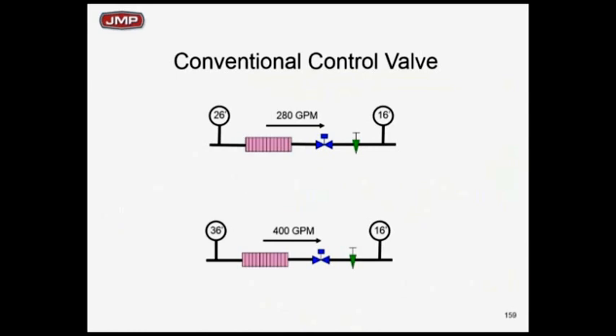I'm going to double the available head, 36 to 16, to 20 feet. I'm not going to change the position of the two-way valve. I'm not going to change the load on the coil. This is instantaneous as this pressure drop changes across the valve, which goes on in big systems every day. What happens to the flow rate? The flow rate jumps from 280 to 400 GPM. Jumps up. Did the cooling coil load change? Not quickly. It's just instantaneous.